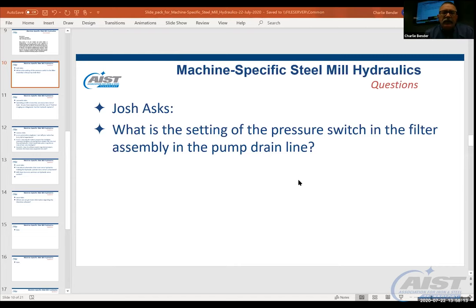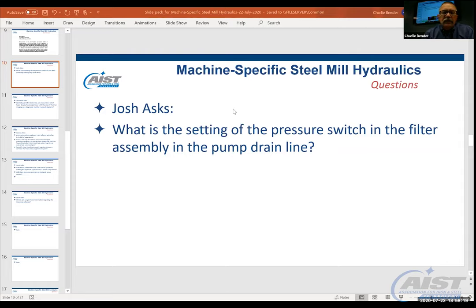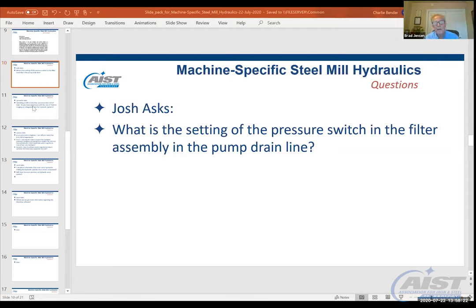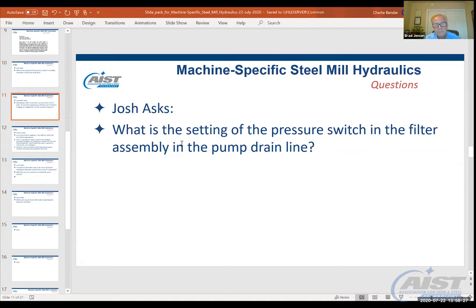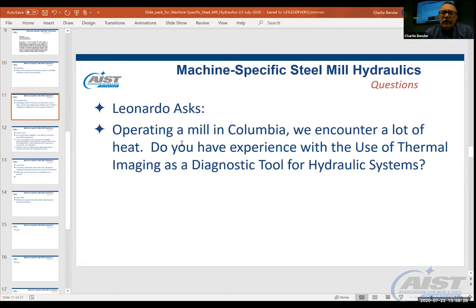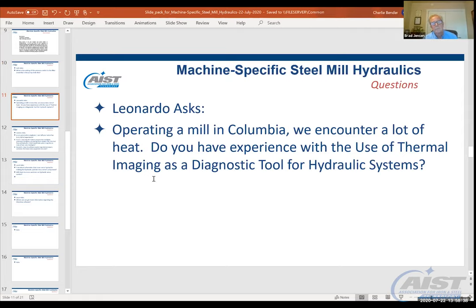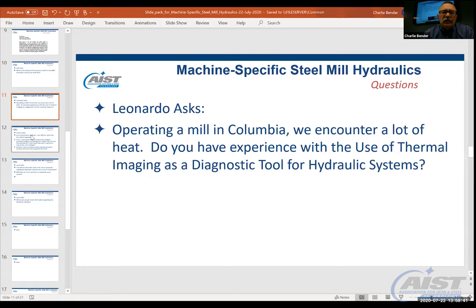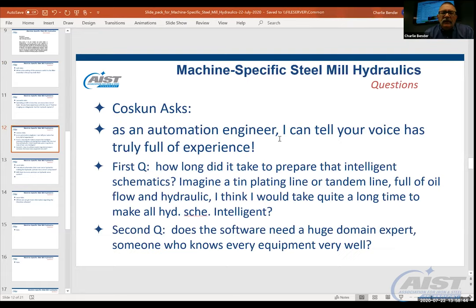You go through the flow meter right back to the tank, not through the filter. Because if you don't have a PSID, 15 PSI differential pressure drop—and I think that is answering your question—across there, you could build back pressure which would lift the shoe off the swash plate. And when that occurs, that pump is going to come apart. So you've got to be very careful about case pressure on an axial piston pump. But I believe that is 15 PSID. Brad, I think if we go through the other questions quickly, we may or may not have time to answer all of them. We'll give contact information so we can go through the questions and have everybody after the 60 minute presentation wait for the answers if they have them. The next question comes from Leonardo.